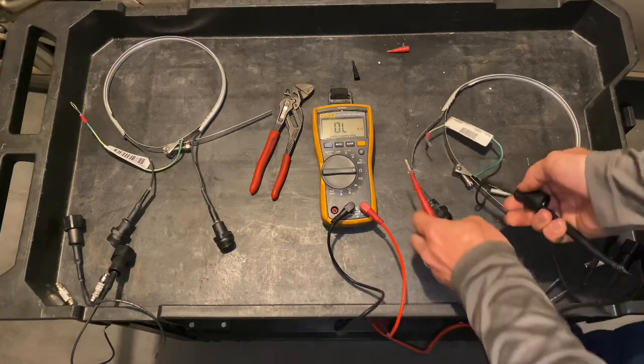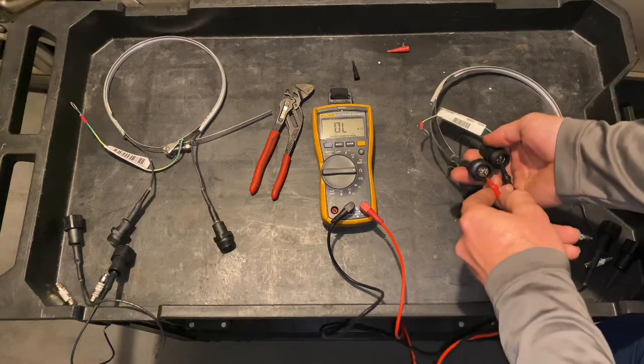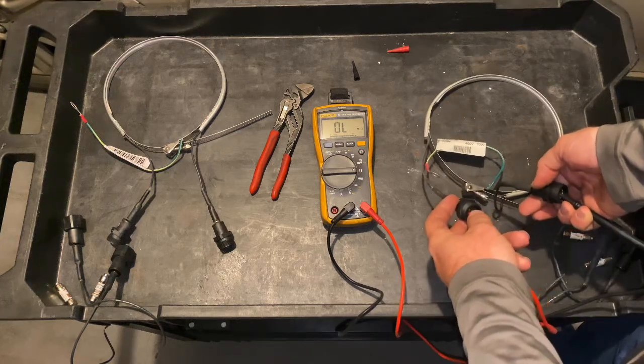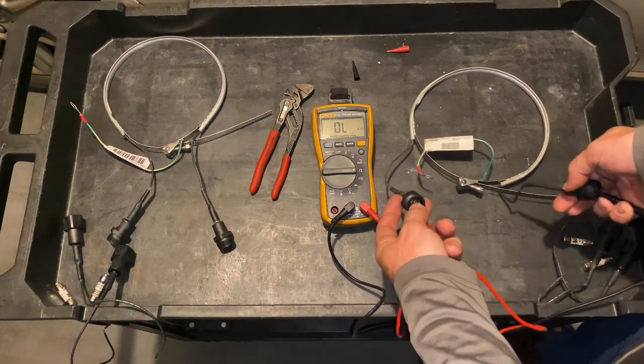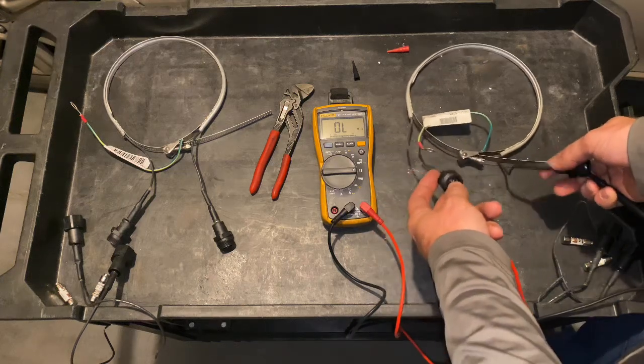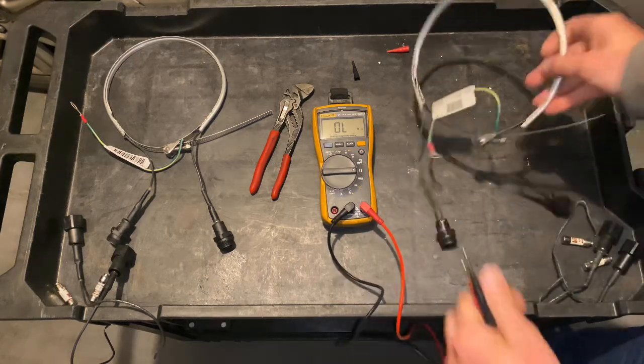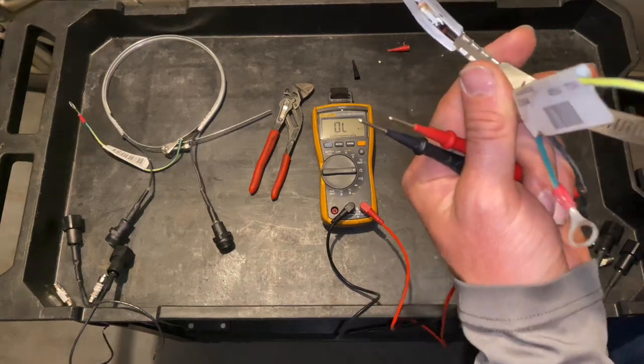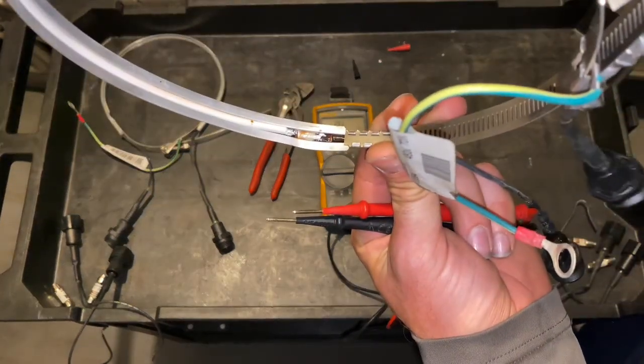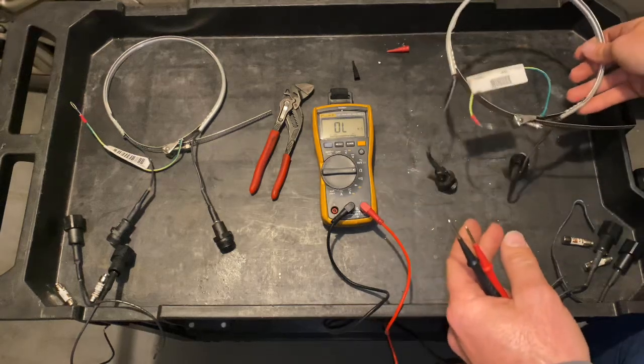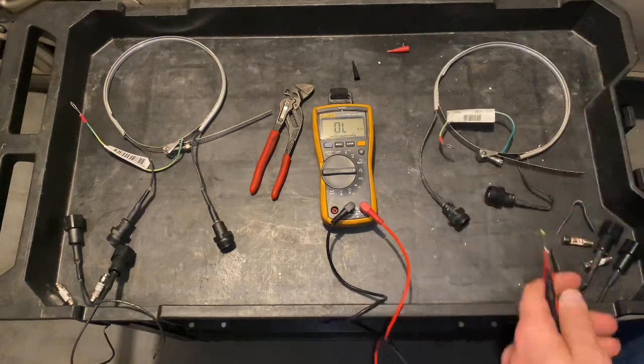So we're going to put our leads going in and going out. As you can see, the meter reads OL, that's because it's actually broken open. As you can see right there, that is actually a broken connection in your heat element.